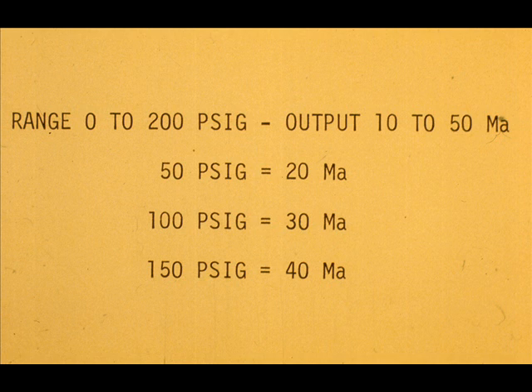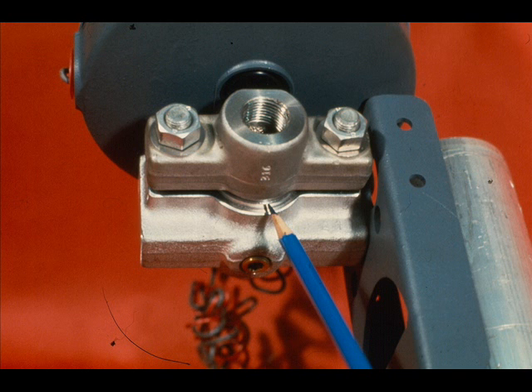Intermediate checks should be made at 50, 100, and 150 PSIG. Next, we have a work request to change the range of our same transmitter — which has the B capsule — to 100 to 400 PSIG.